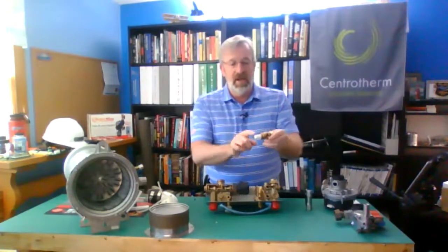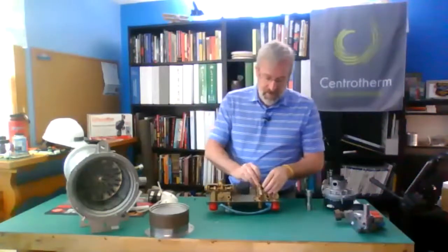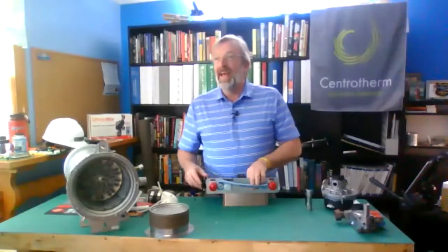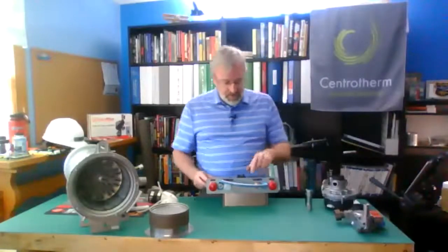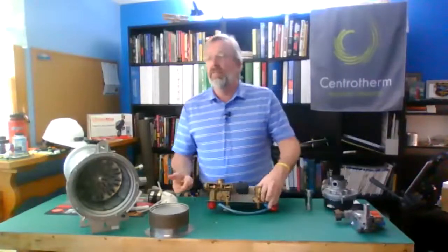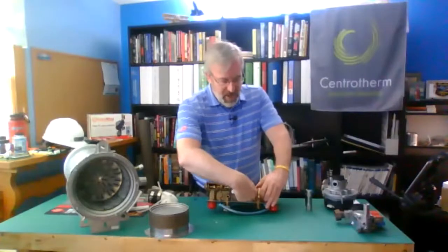A couple of things that are in here, filter. So definitely taking a look at that filter. It's part of a PM. It's not a bad thing to make sure that moves, and maybe put a little vinegar solution in there, or whatever you typically use as a coil cleaner in there. And when I say coil cleaner, if you're an air conditioning guy, not that coil cleaner, but whatever you're using to flush on domestic hot water. In the back there, a little hard to see, but right inside of there, there's a second mesh filter. You can remove that right here. Just so you know, both of these pieces are wet.